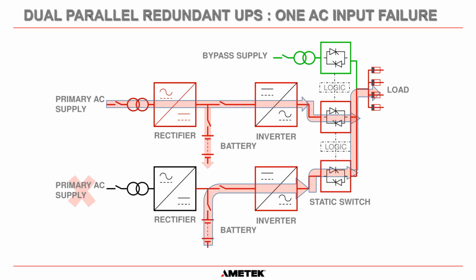Now, on an AMETEK solid-state controls UPS, and you have to check, if you have different manufacturers at your plant, you have to check what the standard design of their systems is. But on our system, if you lose AC power to one of the UPSs in a parallel system, then what's going to happen is that rectifier turns off. And once again, just like you pulling the power out of your laptop, the battery is going to carry on supplying power to the inverter. The inverter is going to remain on, and it will continue to supply power in parallel with the other UPS out to the load circuits. Okay.